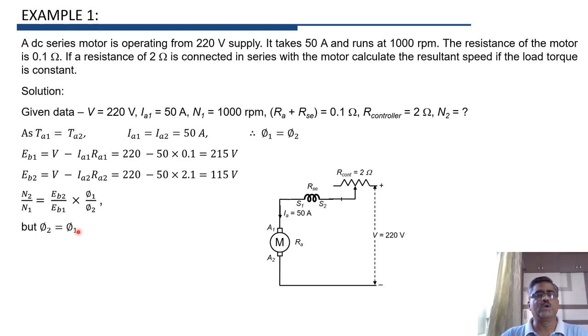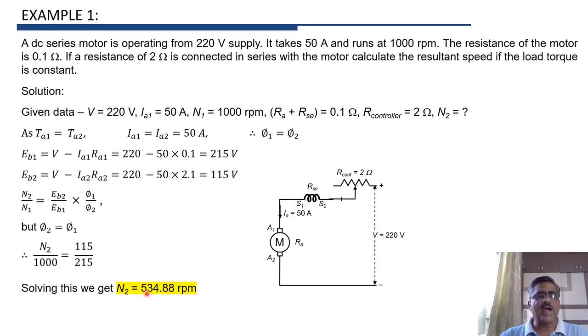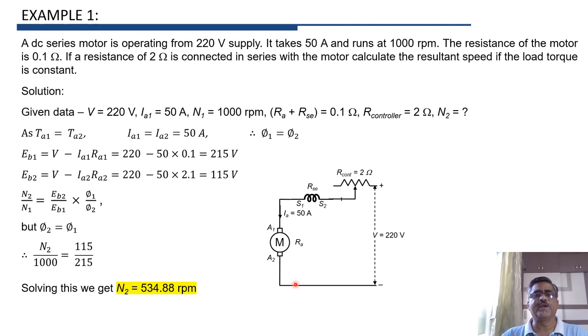Since phi2 equals phi1, N2 upon N1 equals Eb2 upon Eb1. Substituting values: N2 upon 1000 equals 115 upon 215. Solving this gives N2 equals 534.88 rpm. So if a controller resistance of 2 ohm is connected in series with the motor, the speed reduces from 1000 rpm to 534.88 rpm, with load torque maintained constant.